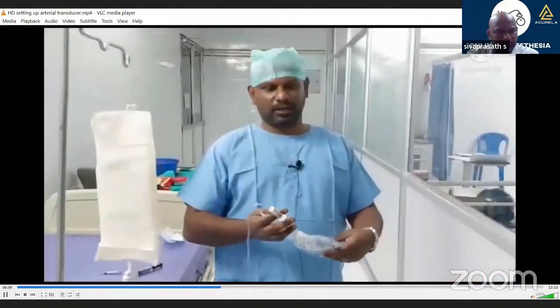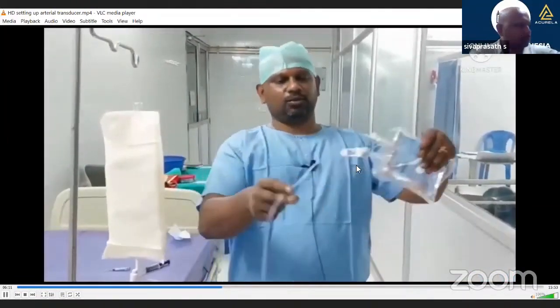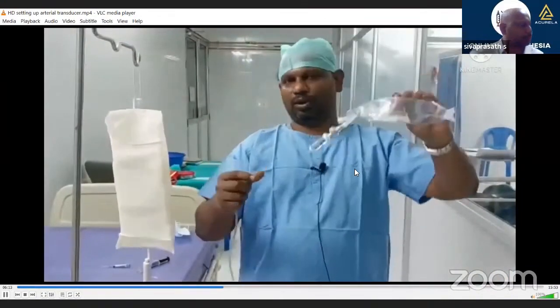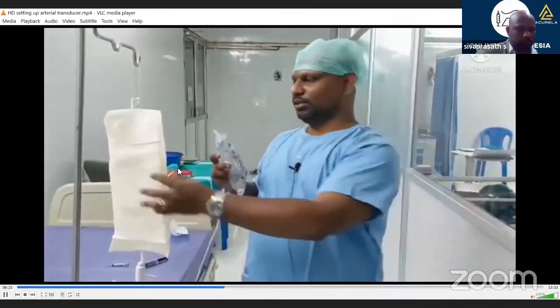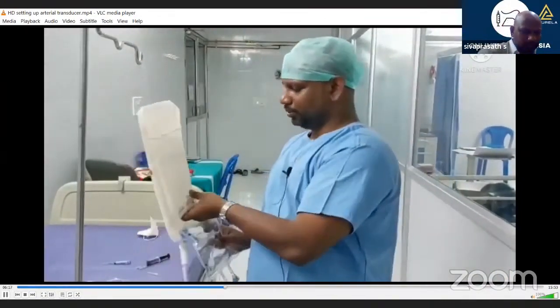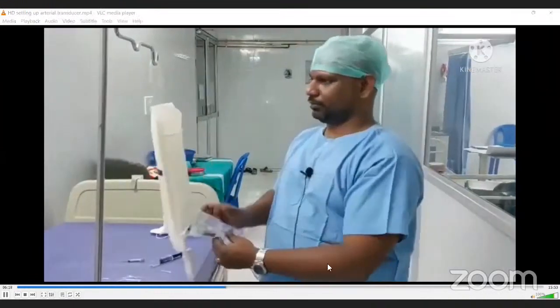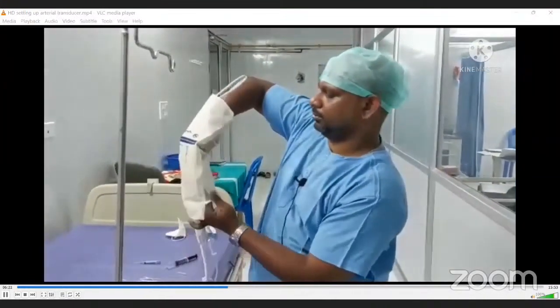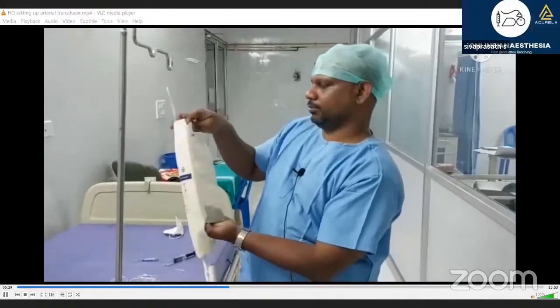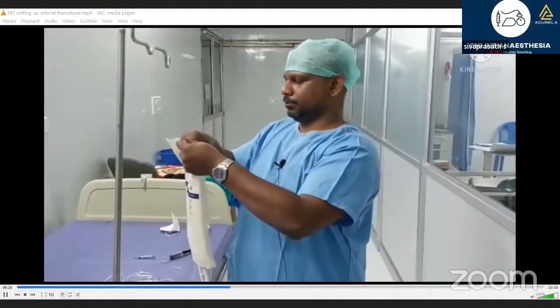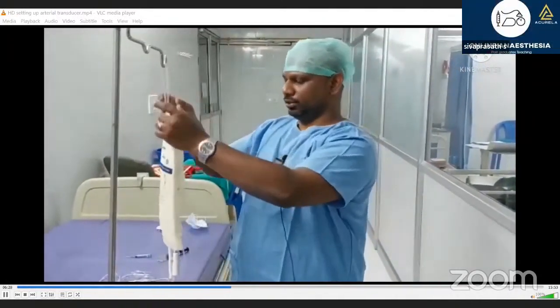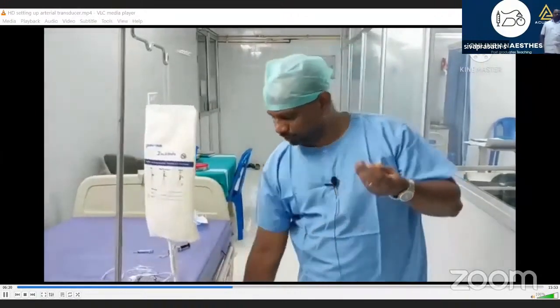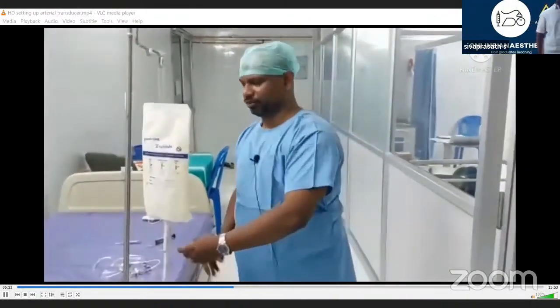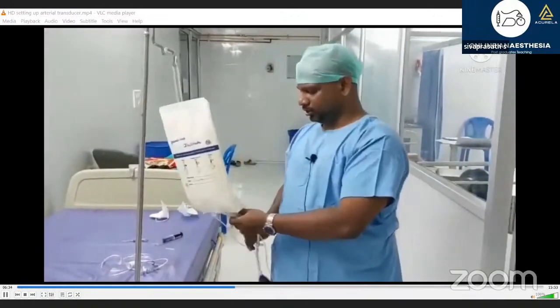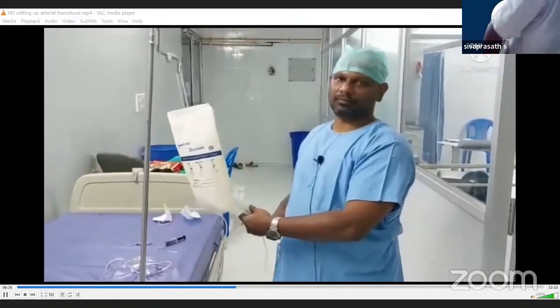Now I have completely de-aired the system. The bag, this tubing, even this air chamber will not contain any air. So now you will have to insert this into a pressure bag system. I have inserted this, hung it on a stand, and you have to inflate the pressure to 300 millimeters of mercury. This should at least be a little bit higher than the arterial pressure.